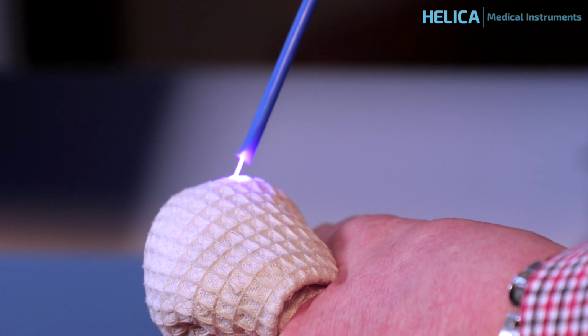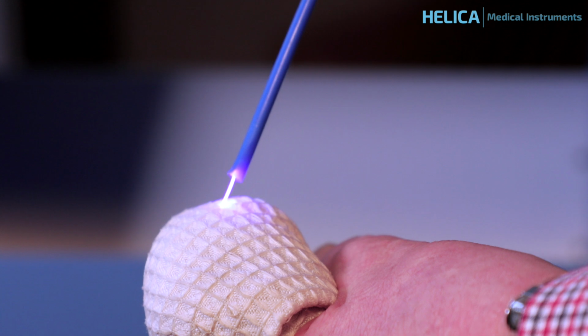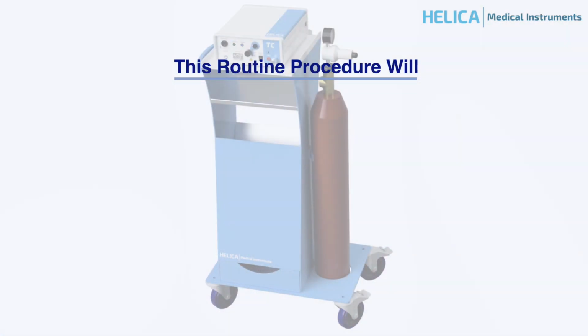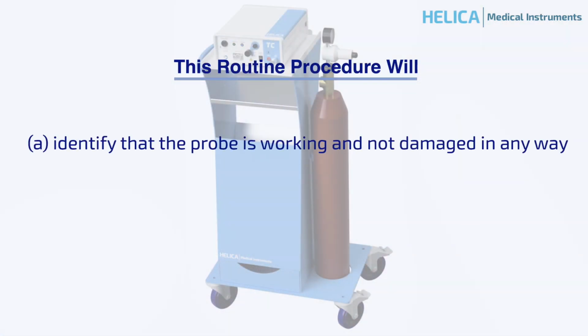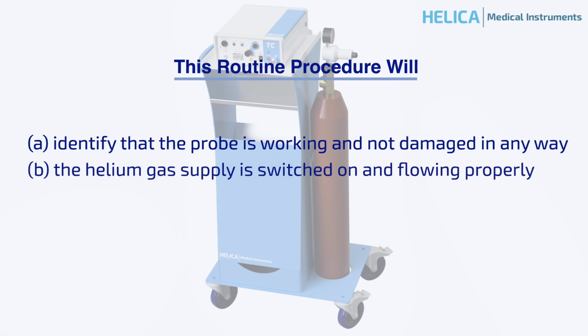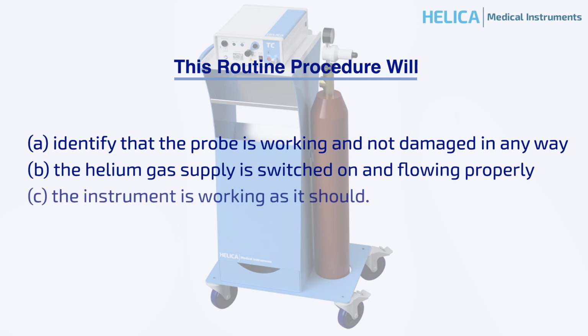There is a slight delay. This procedure, if carried out as routine, will A. identify that the probe is working and not damaged in any way, B. the helium gas supply is switched on and flowing properly, and C. the instrument is working as it should.